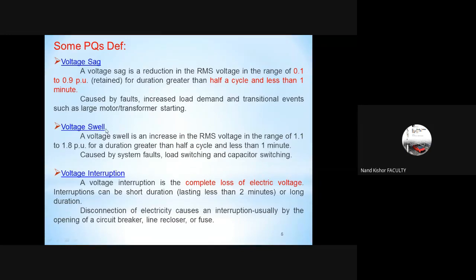Next, a very well known power quality issue that we come across is the voltage swell. In fact, swell is just the opposite of the sag, and it refers to the increase in the RMS value in the range of 1.1 to 1.8 per unit for a duration greater than half cycle. That is because one cycle is 20 milliseconds, so half cycle to a period up to 1 minute. And again, the swell is also caused by faults, load switching or capacitor switching here.